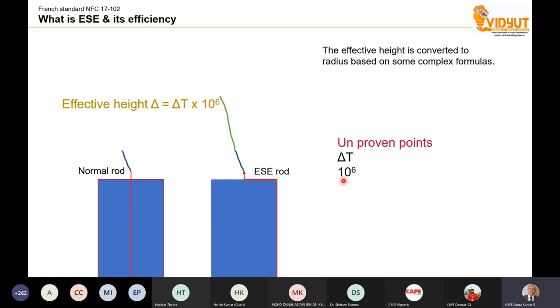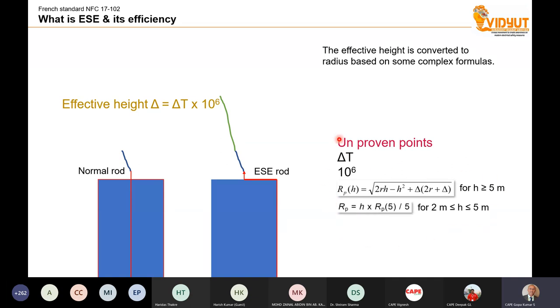Then the speed of the early streamer, 10 to the power of 6, because nowadays there are some reports which say that with the latest modern high speed cameras, people made some research and the speed is not 10 to the power of 6, it is sometimes 10 to the power of 4 or 10 to the power of 5. Then these formulas given in the French standard, these 3 points, the delta T, 10 to the power of 6 and this particular calculation are so far unproven. Because once somebody says that I have a new formula, then it is the responsibility of the person to show that his formula is correct. Until now, the ESE vendors are unable to prove this particular formula.